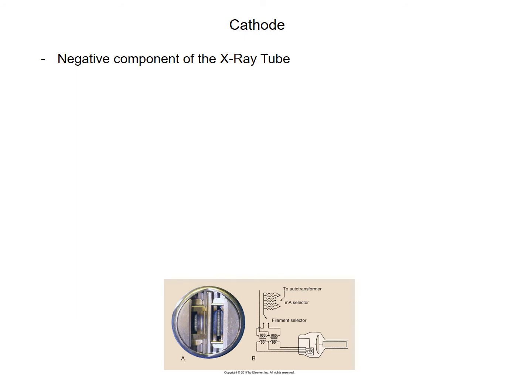Remember, for your filament to select the different MA values, the rheostat or MA selector, which is a variable resistor, is adjusted. And of course, this is then going to feed the electricity into the step down transformer, because remember, you need to heat up the filament. You need a low voltage but a high amperage.